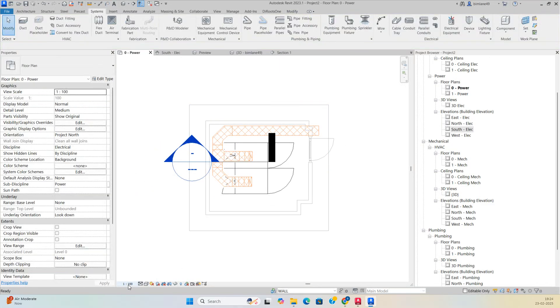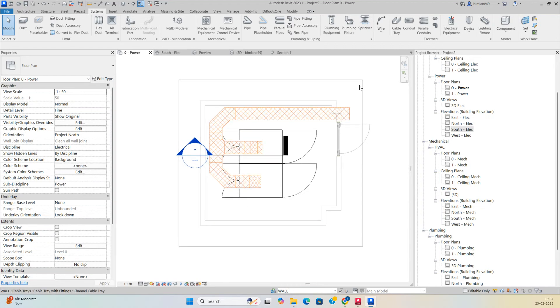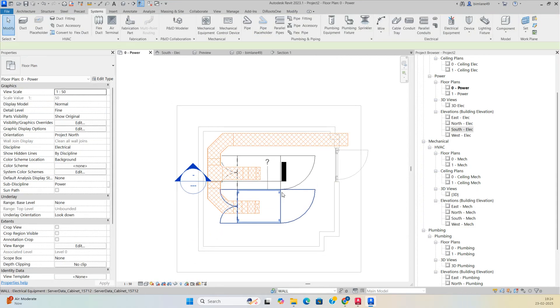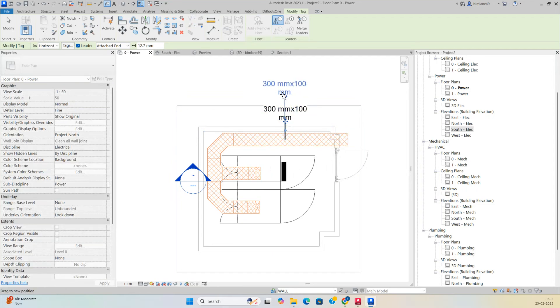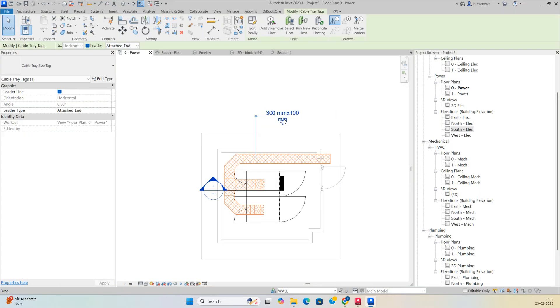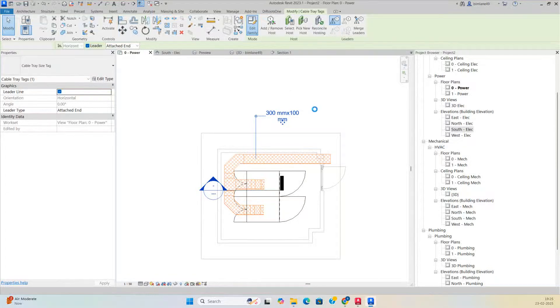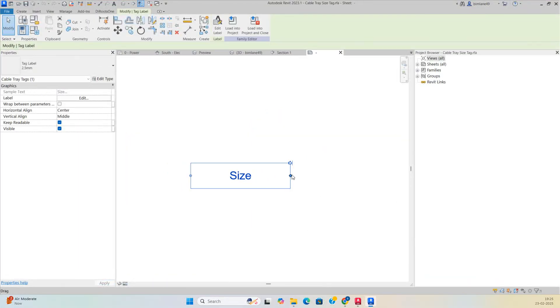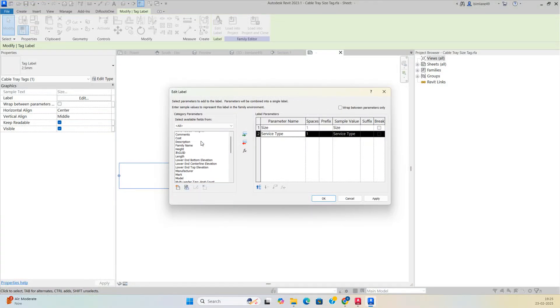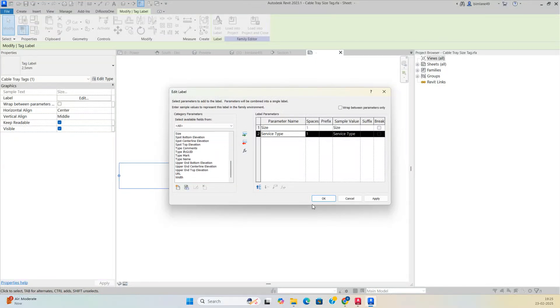Add tags for the cable trays based on service type. Change the scale and place tags on each cable tray. To customize the tag, go to Edit Family, add the Service Type parameter and other fields like Bottom Elevation, then stretch and modify as needed.